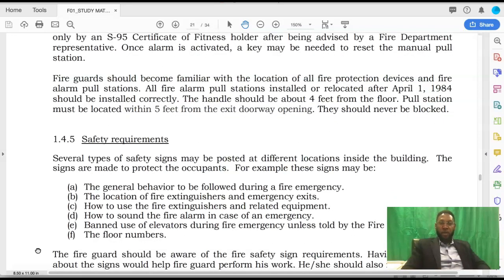Fire guards should become familiar with the locations of all fire protection devices and fire alarm pull stations. All fire alarm pull stations installed or relocated after April 1st, 1984 should be installed correctly. The handles should be about 4 feet from the floor. Pull stations must be located within 5 feet from the exit doorway opening. They should never be blocked. And that is a test question. The handles should be about 4 feet from the floor. Pull stations must be located within 5 feet of the exit doorway opening, and they should never be blocked.